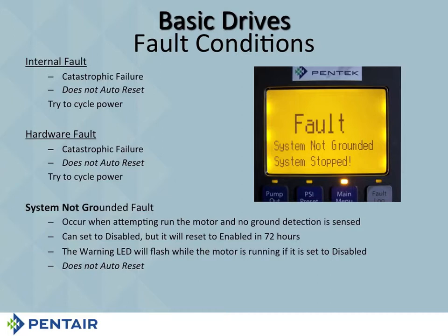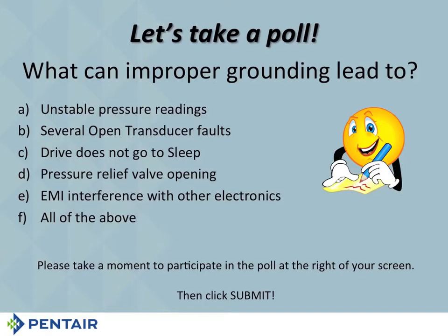The last one there is system not grounded fault. If you do not connect your ground wire all the way back to the main breaker box, or if you try to put more than one ground wire in, you're going to have problems. And the system is going to say, system not grounded. It will turn the pump off. You can go out there and disable that, but it will only be disabled for 72 hours and it's going to turn back on. So the bottom line is, when it says system not grounded, if it's 11 o'clock at night and you just want to go home, disable it. But remember, in 3 days, you got to get out there sometime in the next 3 days to fix it. Otherwise, you're stuck.